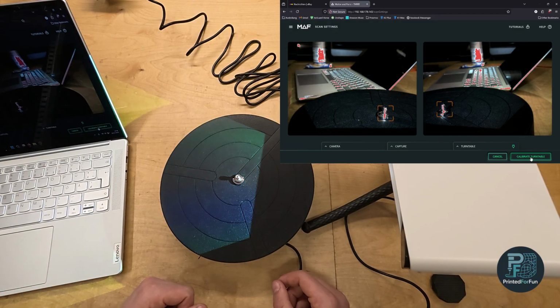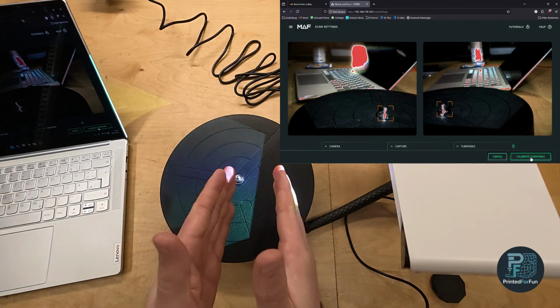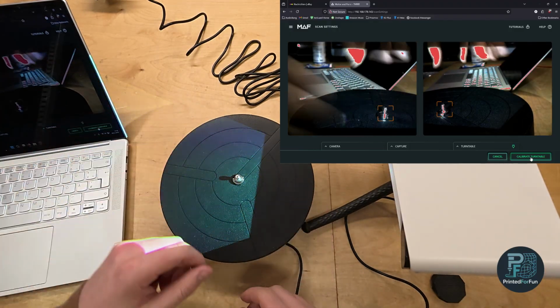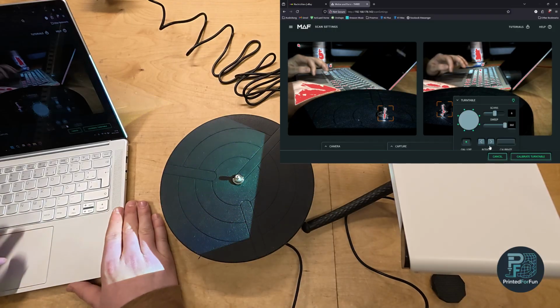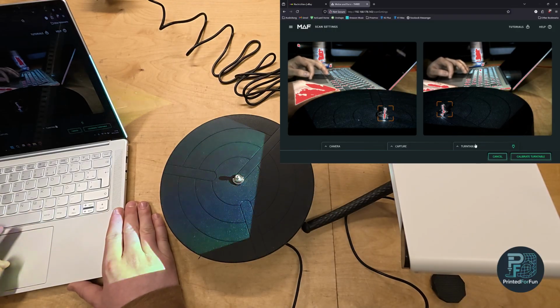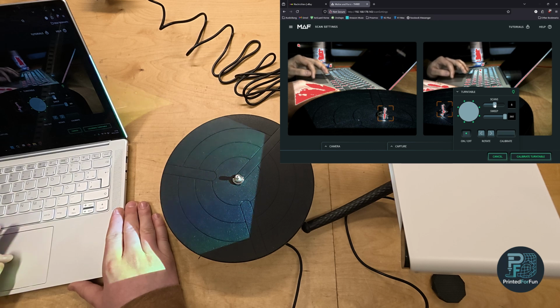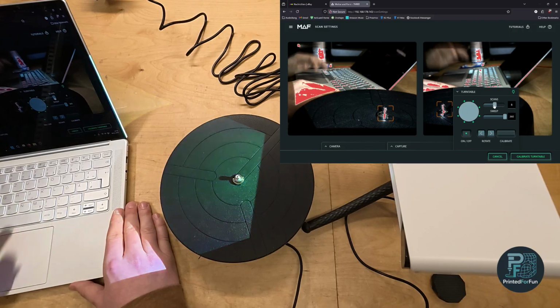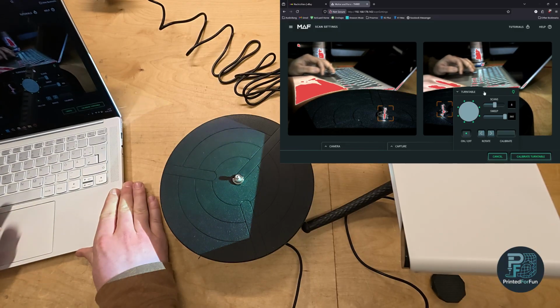of the single scans, because it does one frame, then it rotates a bit, it does the next frame, and how many frames it takes can be set in the turntable tab here. As you can see, I have this slider, and it directly gives me an animation of how it will look, or how many scans it will perform. For normal scans or medium density scans, 8 is fine. For high density, 10 could be beneficial, but keep in mind the processing time increases if you also start increasing all parameters.